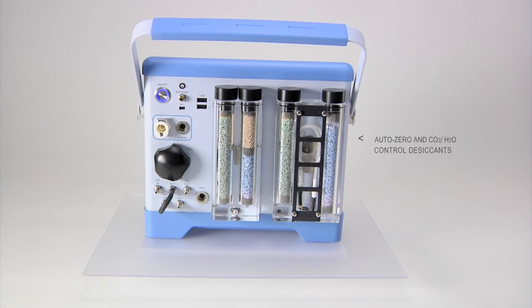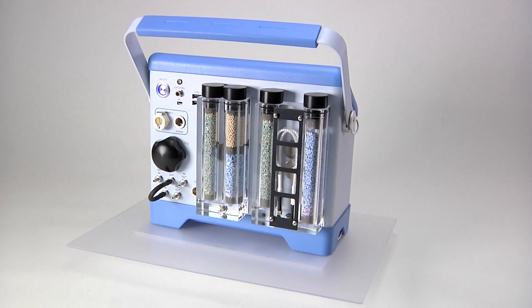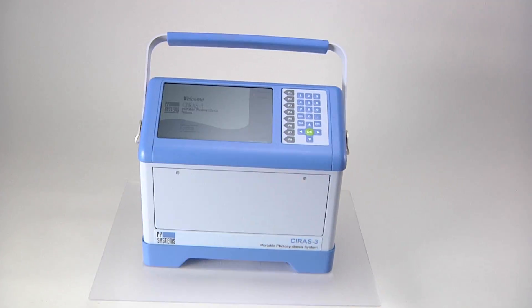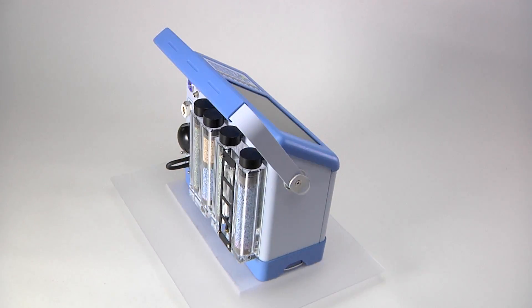The rear panel reveals the conditioning desiccants for AutoZero, CO2, and H2O control. It also includes a CO2 cylinder holder and regulator, leaf cuvette connections, system power and USB ports for data management. The CIRAS-3 can also be used as a stand-alone CO2 and H2O gas analyzer, making it extremely easy to use with the end-user's own custom-designed chambers.